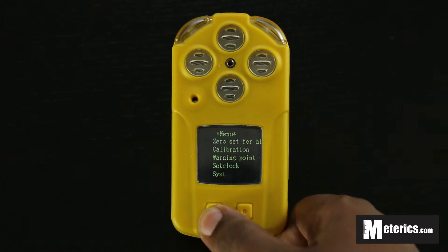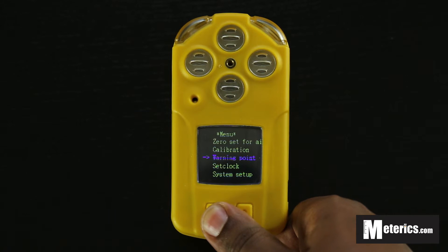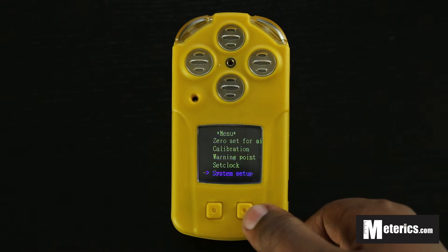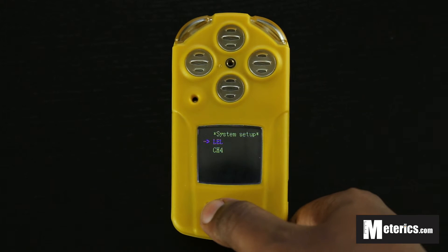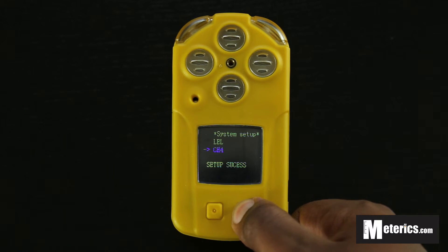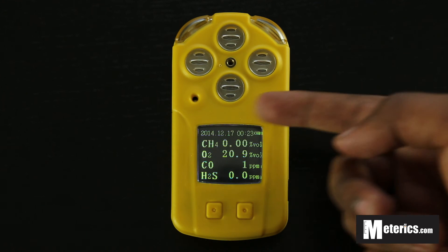To change the gas type, hold the menu button. The menu options are: Zero Set (resets everything), Calibration, Warning Point (where you set the alarms), Set Clock (change date and time), and System Setup. Go to System Setup, hold the key for about a second, and you can change from LEL to methane gas. Push to select, then hold in for a second — 'Setup Success' is confirmed.